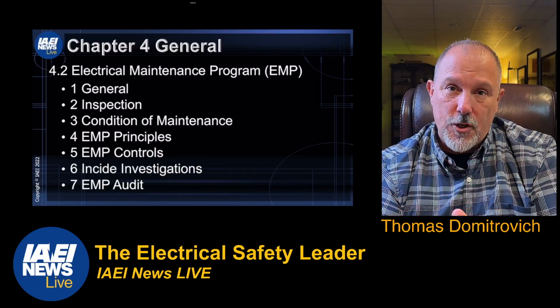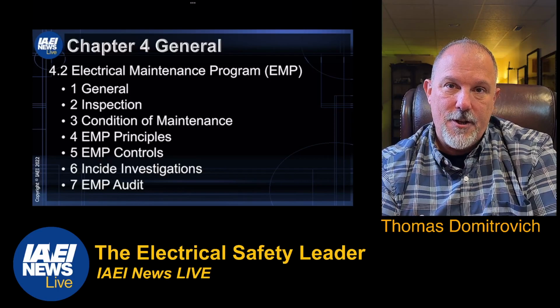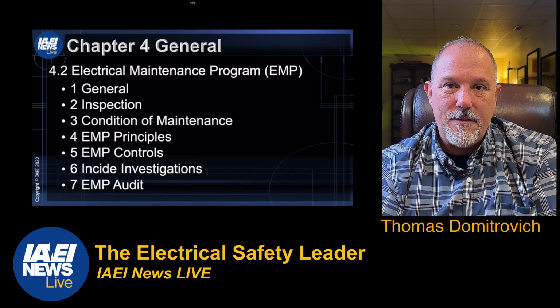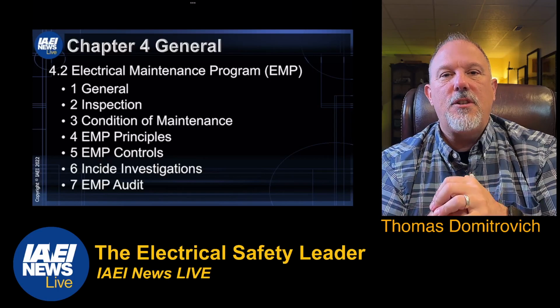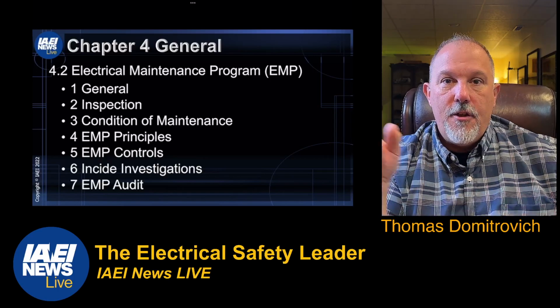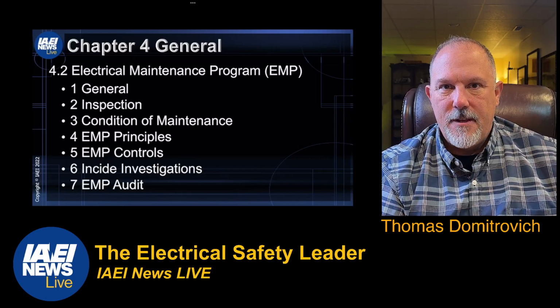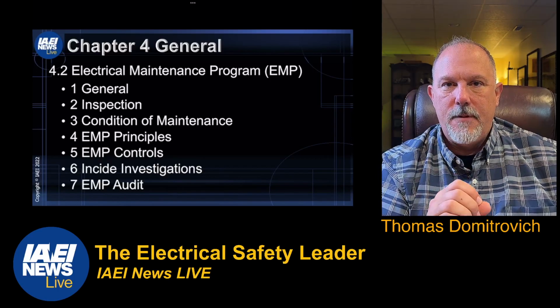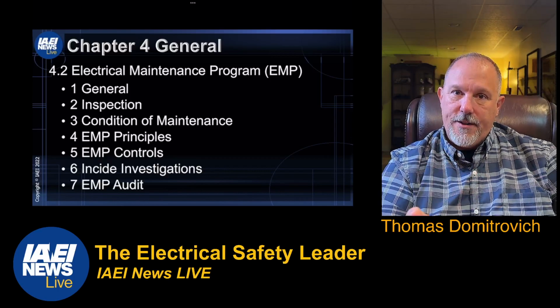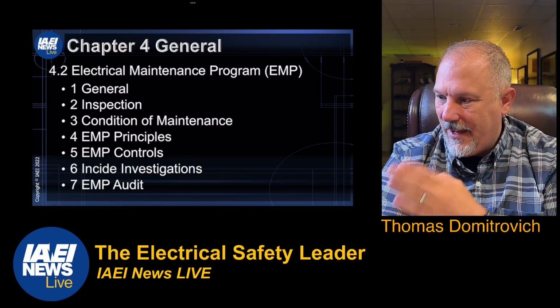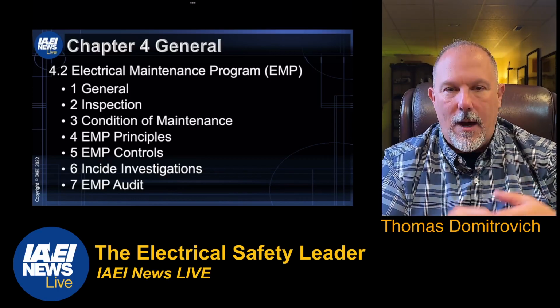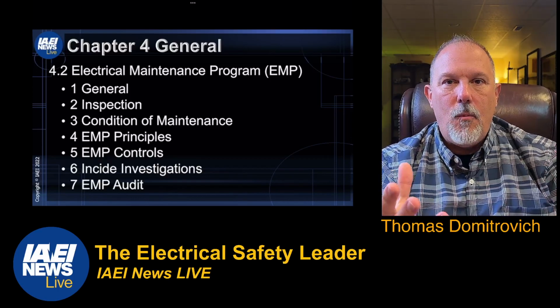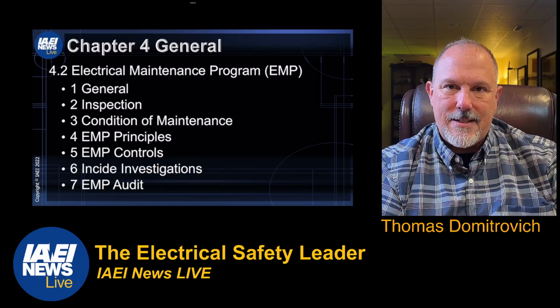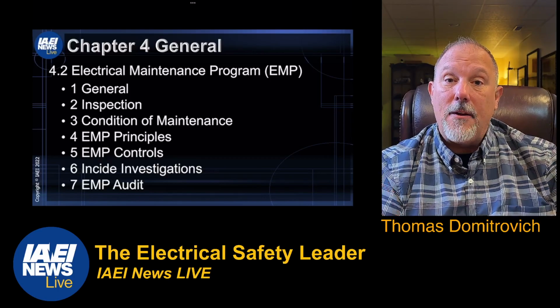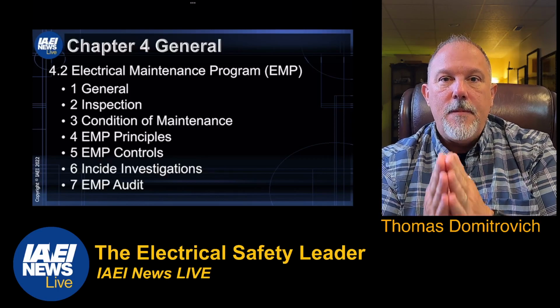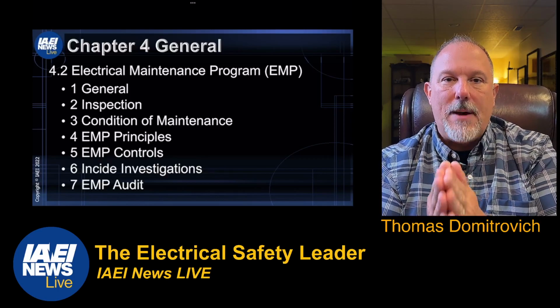For example, you have a short circuit in your facility. From a grounding and bonding perspective, when you have a ground fault in your power distribution system, you put stress throughout that path of current flowing in the system. Wherever that ground fault was, in your investigation you may want to understand why. But also, the performance of your grounding and bonding system, is the integrity still there? You've got to think about the stress you just placed on the power distribution system.